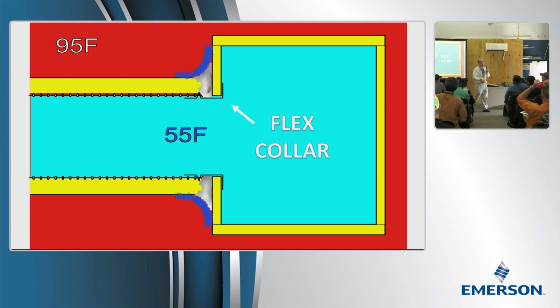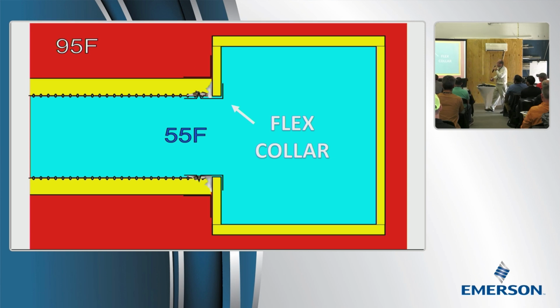And so we don't want to pinch the insulation. We want it fluffed out around the collar. We don't want mastic piled up like I show it right here, because mastic is not insulation. That mastic will just turn black and get damp. We want it like that. We want just enough of an air barrier to carry the air barrier from the inside to the outside, and then we want enough insulation to keep that whole collar underneath. In Florida, you have to tape the outside liner. I know in some states you don't have to do that, but in Florida's building code, you do have to, even if you seal the inside. You can't just fold the outside around and panduit it. You can't do that in Florida. You have to seal it.